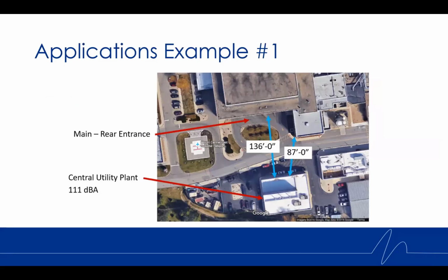So let's look at the first example. Now this is very typical. This was a hospital that had a new central utility plant built right across the street. And we were finding that as people were entering and leaving the hospital, the noise level was quite loud. Actually measured at the central utility plant, it's about 111 dBA. And to give you some context, typical noise bylaws are around 50 to 60 dBA at a property line. So this was quite excessive, and excess noise in this case.